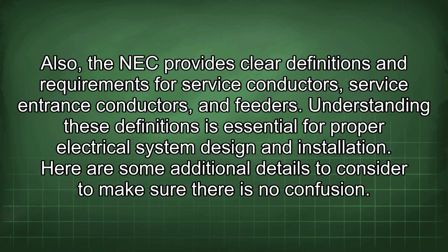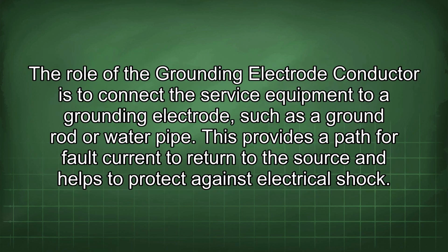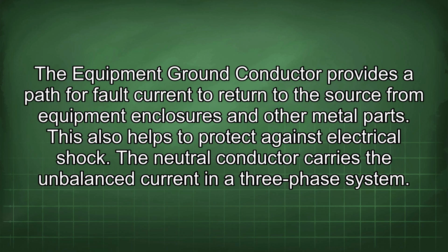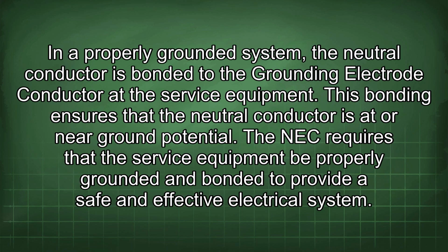Here are some additional details to consider to make sure there is no confusion. The role of the grounding electrode conductor is to connect the service equipment to a grounding electrode, such as a ground rod or water pipe. This provides a path for fault current to return to the source and helps to protect against electrical shock. The equipment ground conductor provides a path for fault current to return to the source from equipment enclosures and other metal parts. This also helps to protect against electrical shock. The neutral conductor carries the unbalanced current in a three-phase system. In a properly grounded system, the neutral conductor is bonded to the grounding electrode conductor at the service equipment. This bonding ensures that the neutral conductor is at or near ground potential.